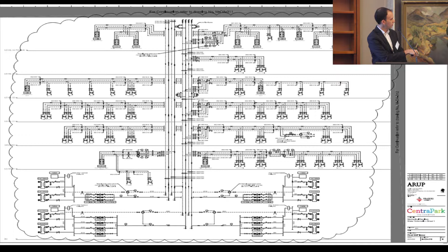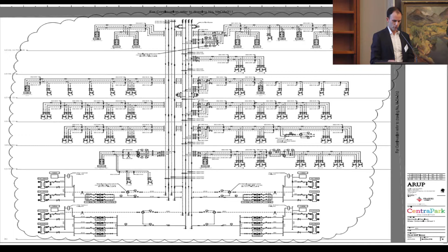The water schematic on screen shows some of the energy transfer stations at the bottom, which are essentially a heat exchanger connecting to the central plant, and then a group of pumping stations. While it looks simple enough, just heat exchangers at the bottom of the building, a lot of thought was put into how they would be configured to match the tiling and the stratums above for ease of metering, which was a very important component of the design.